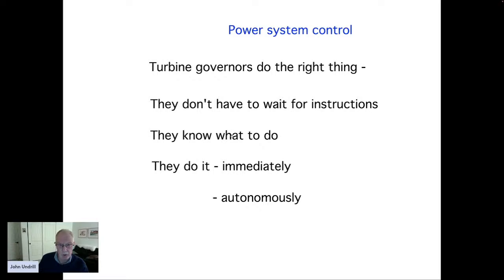And I won't go back to the slide, but the time constants characterizing the governors are of the range of 50 milliseconds to perhaps 100 milliseconds. So the present power system has a strange characteristic. The thing that's being controlled has long time constants, 5 and 7 seconds. The controls that are operating on it are mechanical and thermodynamic and hydraulic, and they're characterized by time constants of tens of milliseconds. It's rather impressive to stand in the turbine pit of a hydro turbine when one of these events happens, perhaps in a test, and see this very large machinery, hydraulic jacks with 50 centimeters diameter and a travel of a meter, moving with a time constant of perhaps 300 milliseconds.